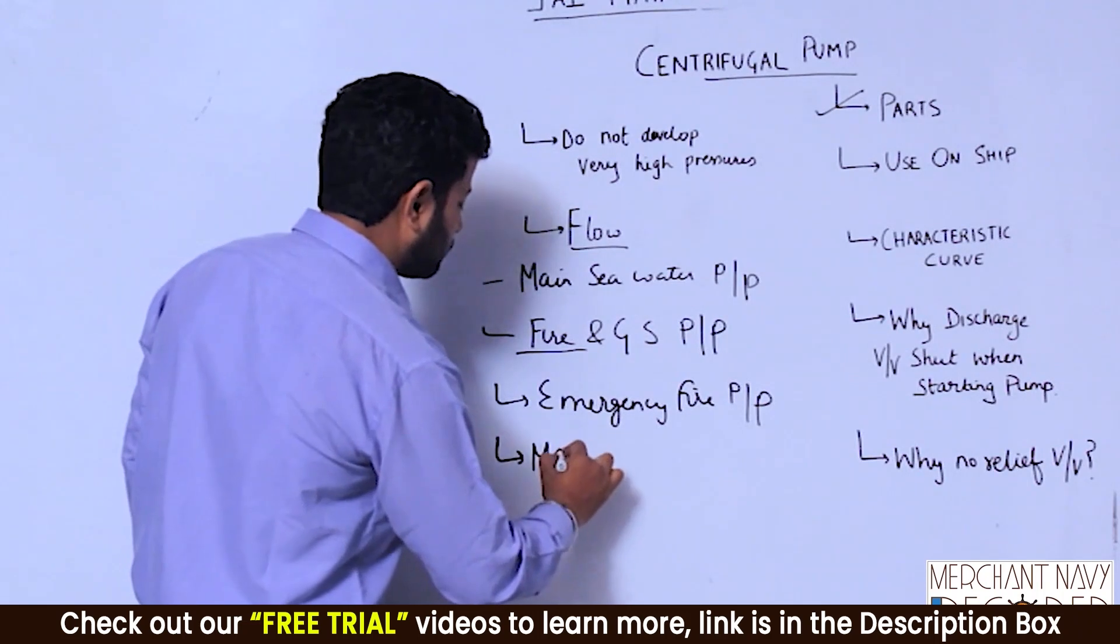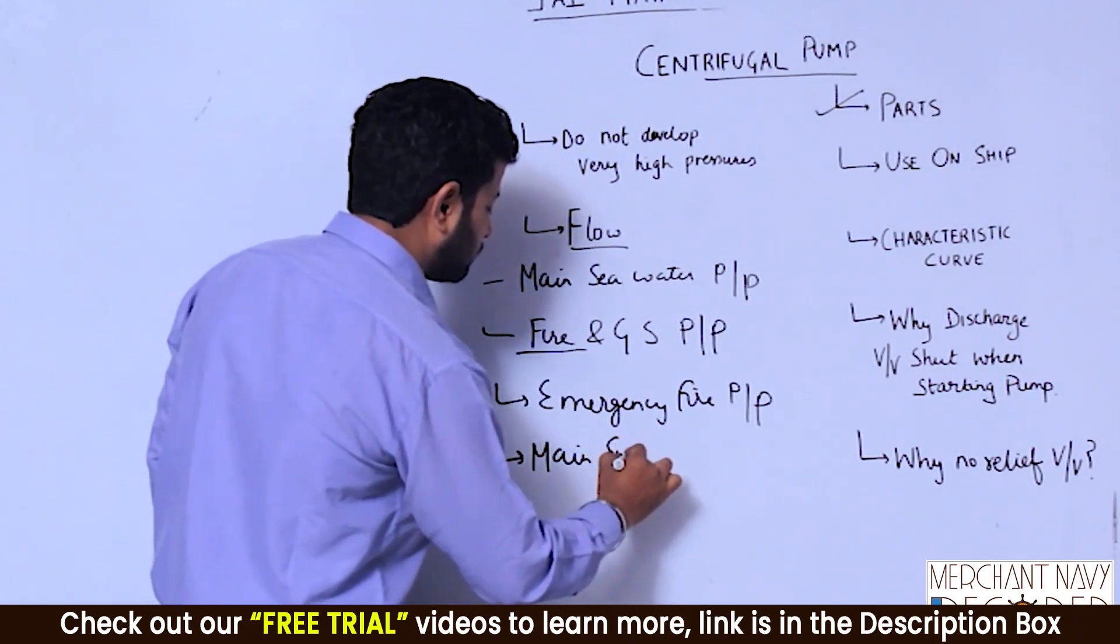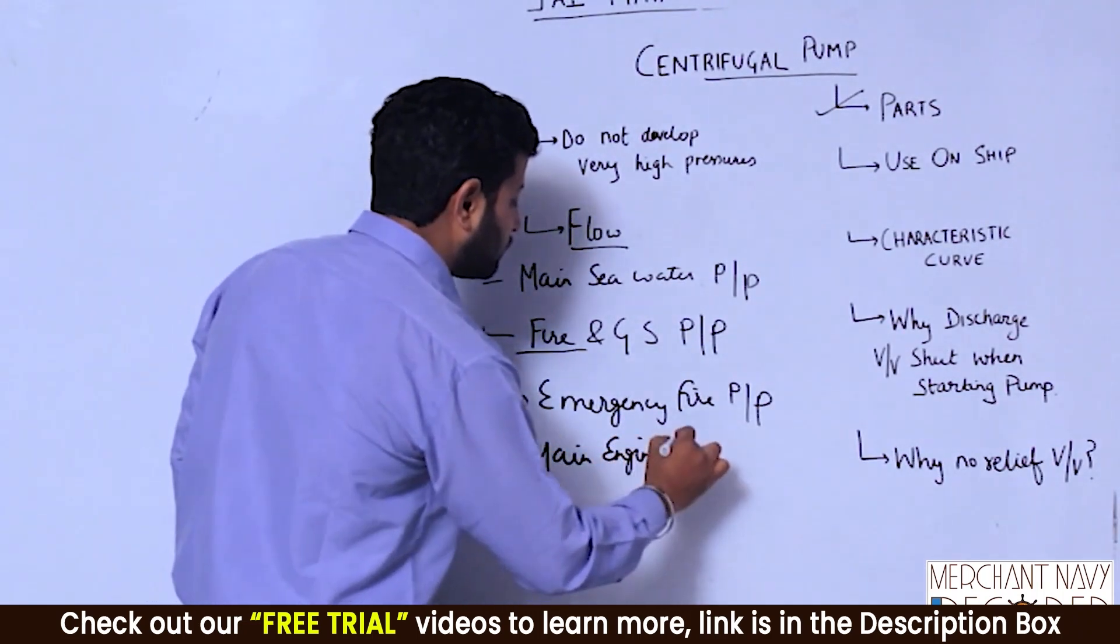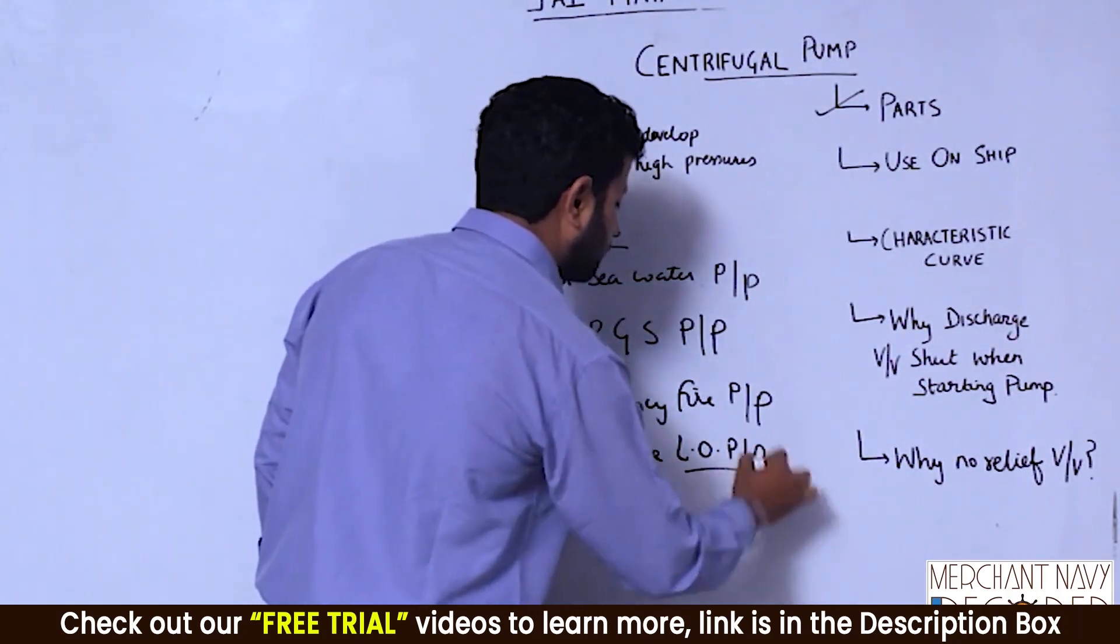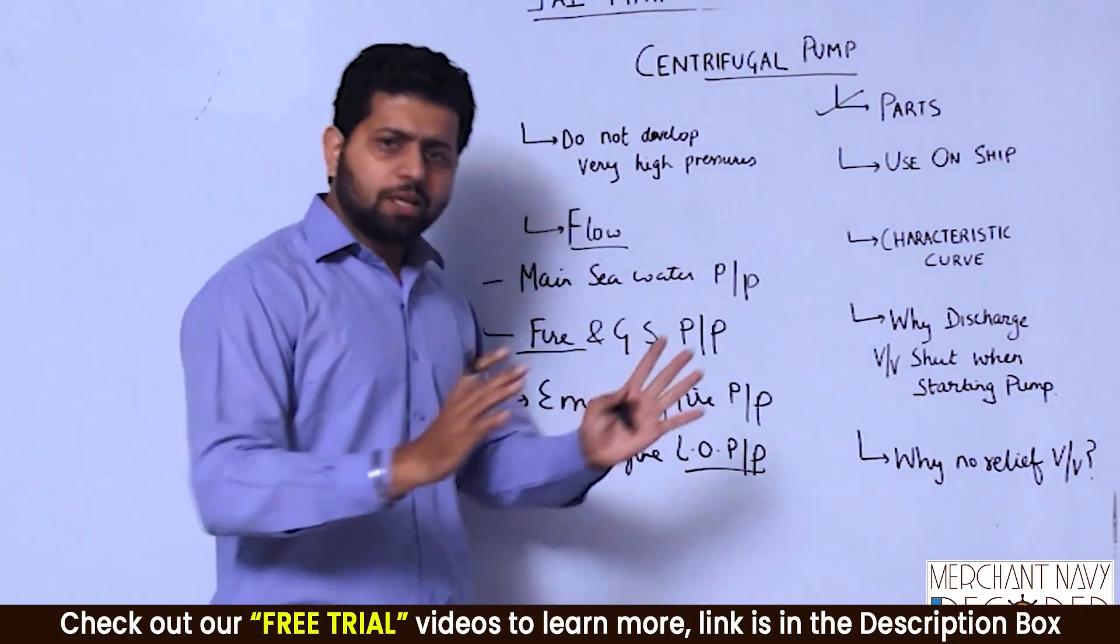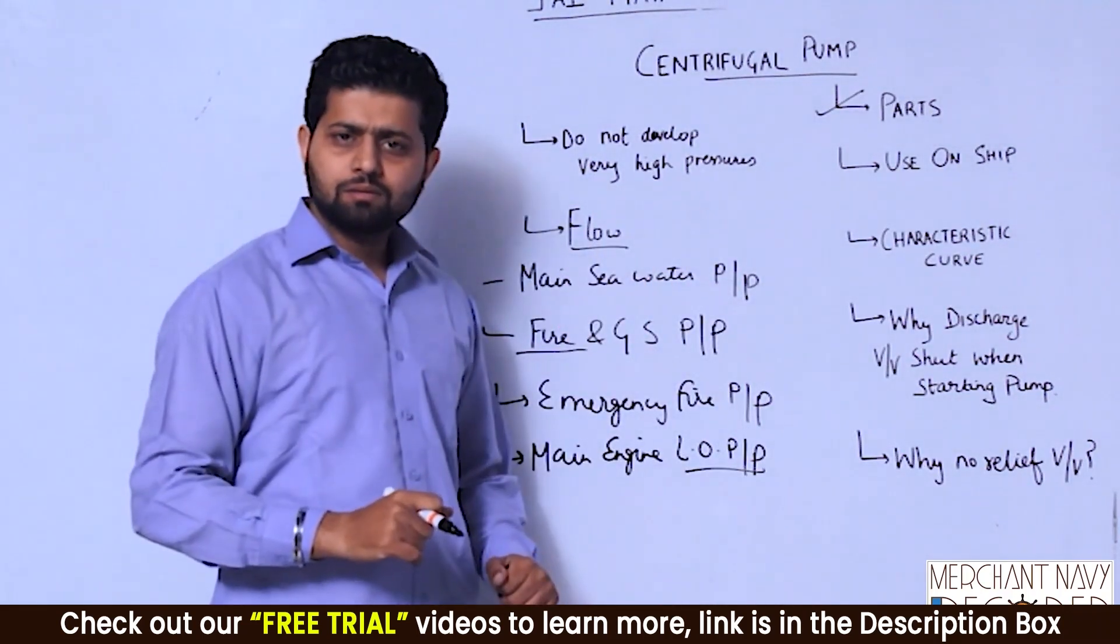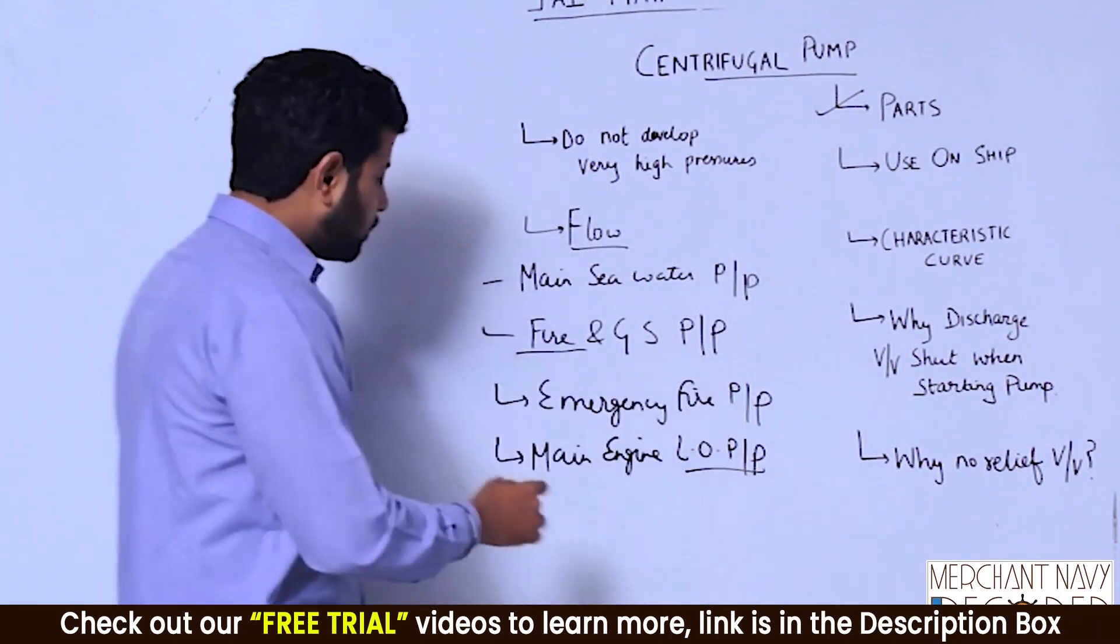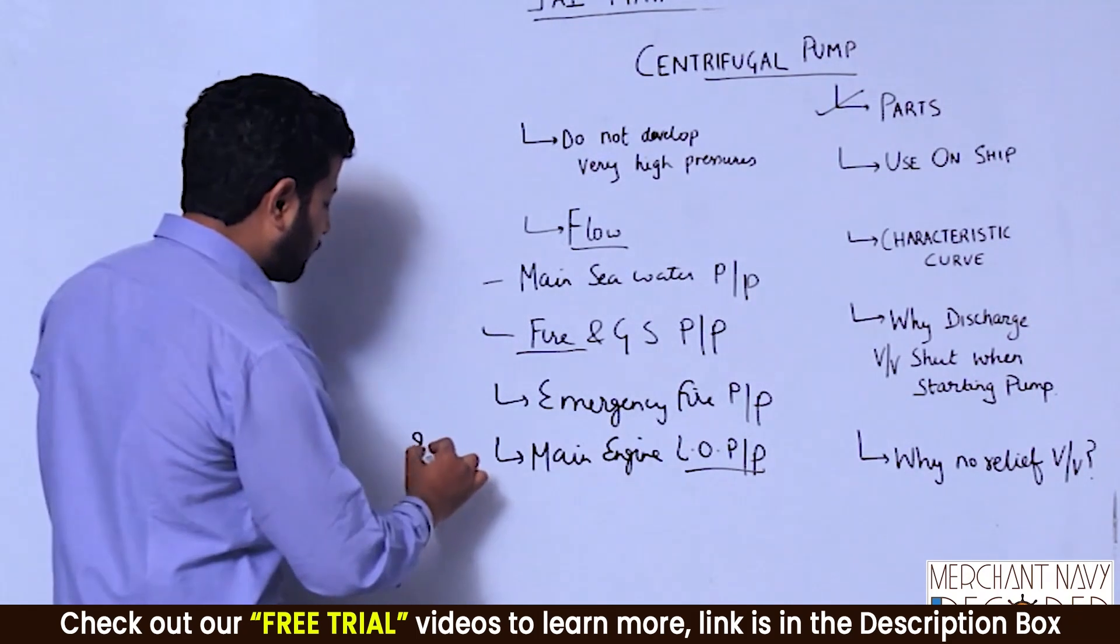Main engine lube oil pump. This is also a centrifugal pump because not enough pressure required. Flow is required. Lube oil pump delivers pressures at 2 to 2.5 bar.